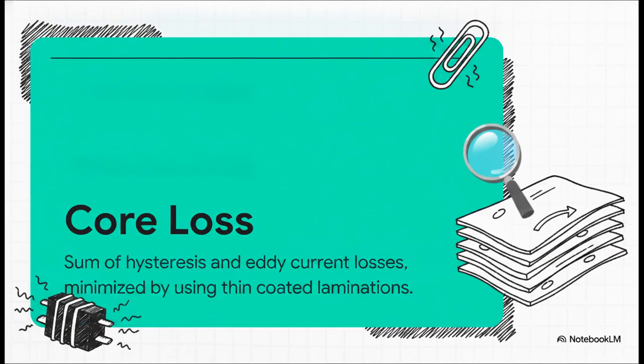It creates what we call core losses. Core loss is essentially the sum of two things: hysteresis loss and eddy current loss. Think of hysteresis like when you take a paperclip and bend it back and forth really fast and it gets super hot. That's what's happening here. Heat is generated just from realigning the magnetic domains 50 or 60 times a second. Then you've got eddy currents, which are circulating currents trapped directly in the steel. To fight this, engineers don't use just a solid block of iron. Instead, they stack thousands of super thin, individually coated steel laminations, kind of like the pages of a really heavy book.